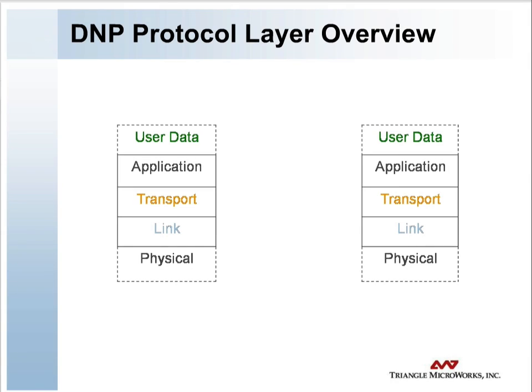DNP-3 is a layered protocol. However, rather than adhering to the OSI, or Open System Interconnection, seven-layer protocol, DNP-3 adheres to a simplified three-layer standard proposed by the IEC, the International Electrotechnical Commission, for more basic implementations. IEC calls this the Enhanced Performance Architecture, or EPA.